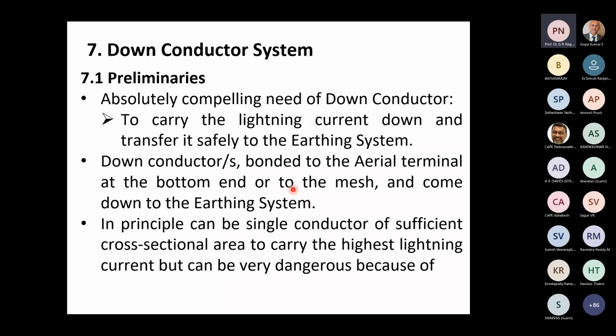Now, down conductors are bonded to the air terminals at the bottom, or to the mesh, and come down to the earthing system. I must again mention here, all the corners must be provided with lightning rods. Along the edges also, the presence of lightning rods may be necessary, may be essential. Now, all the bottoms of the air terminals must be bonded together. This is a very, very important consideration. All these are to be bonded together by a metallic strip that will go along the corner of the building.